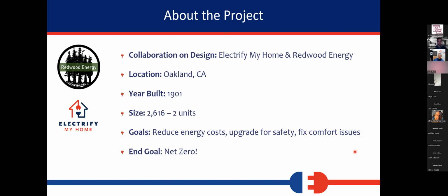They had this problem where the front bedroom never got warm because it had dual wall exposure, and on the third wall was the garage with a foundation wall coming up. They complained that when they turned on the heater, this room was always cold. What we discovered is that it wasn't that room's fault - the rest of the house was heating up so rapidly that there wasn't enough air or energy being delivered into that front room to get it up to speed. They tried all kinds of things until they just shut it off and put space heaters in a couple places.